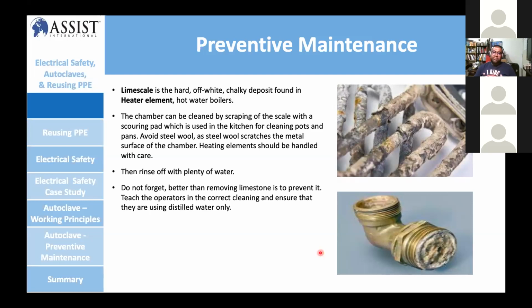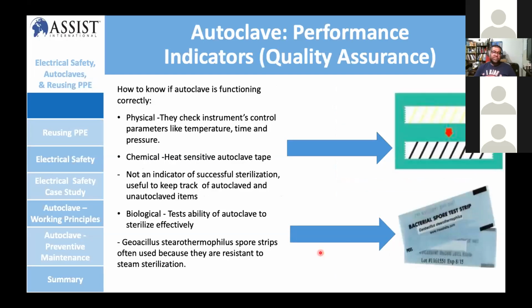So to do a performance indicator test on autoclave quality assurance, there are a few ways that you normally do it. You can use the physical check, using an instrument to check the temperature, pressure, all that. And you can use chemically sensitive autoclave tape. You can see the before and after. Before is the yellow line, and after the test the line becomes black.